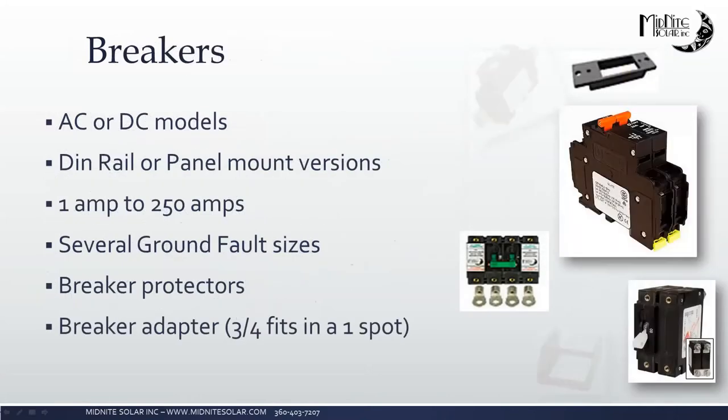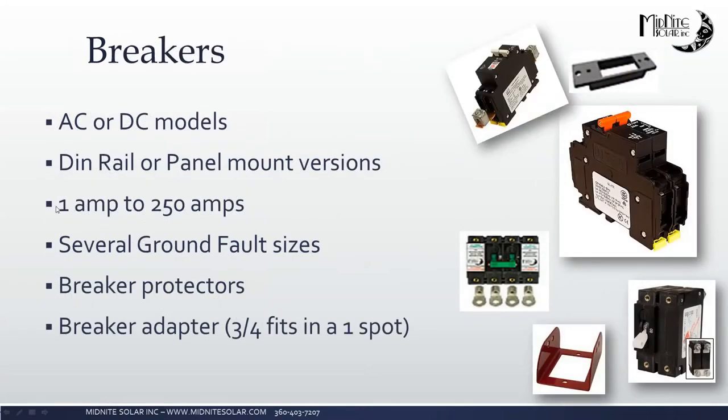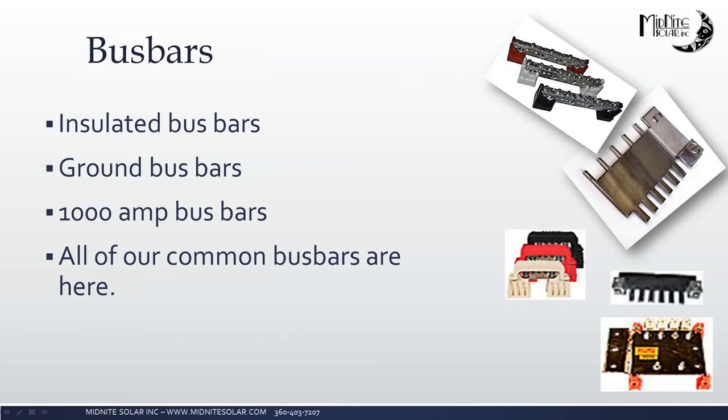Moving on to our breakers — all MidNite circuit breakers can be used at 100% of the rated current when mounted in one of our MidNite enclosures. They come in AC and DC, with DIN rail and panel mount versions, ranging from 1 amp to 250 amps. We have ground fault, remote breakers for rapid shutdown equipment, breaker protectors, and a breaker adapter that allows you to use a 3/4-inch breaker in a 1-inch slot since 3/4-inch breakers are more available. We also have a full range of bus bars — insulated, grounding, and 1,000-amp — including replacements for our combiner boxes.